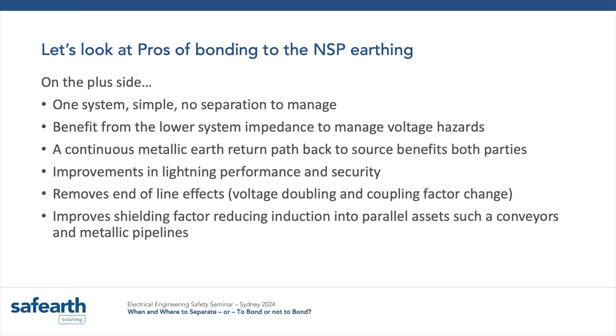Now this is probably more of their problem, but if you own the line across your site, like these guys did in WA - there's a 66 kV power line on the left-hand side there, running for many, many kilometres parallel to that conveyor. If you don't earth the line well, without a good earth wire on it, there's no shielding provided by that system, and you can create really big volts on the conveyor.